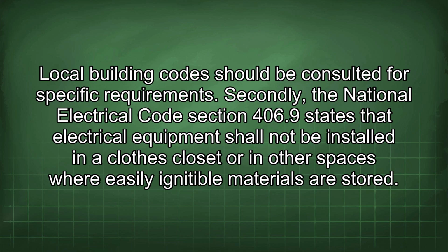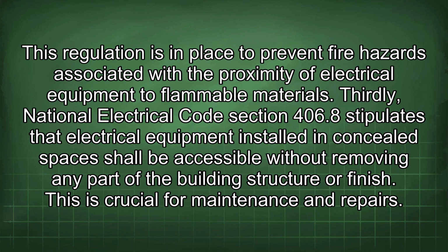Secondly, the National Electrical Code section 406.9 states that electrical equipment shall not be installed in a clothes closet or in other spaces where easily ignitable materials are stored. This regulation is in place to prevent fire hazards associated with the proximity of electrical equipment to flammable materials. Thirdly, National Electrical Code section 406.8 stipulates that electrical equipment installed in concealed spaces shall be accessible without removing any part of the building structure or finish. This is crucial for maintenance and repairs.